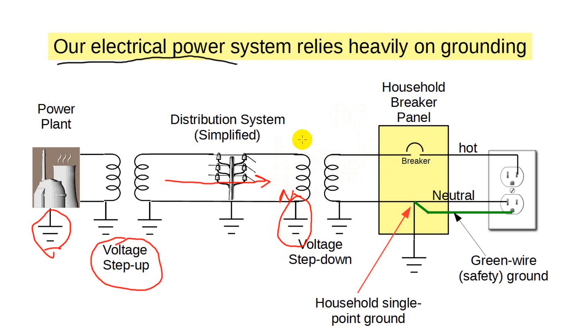When the local step-down transformer is encountered, again the neutral side is held at ground potential. This goes into your house and note here an interesting thing. There is a single point ground. The neutral connects to it. A wire exits your entrance point to a ground rod and the safety ground or green wire ground is connected at this point too.